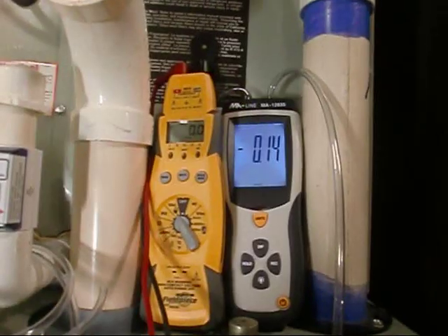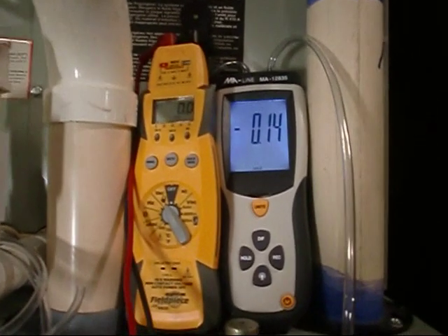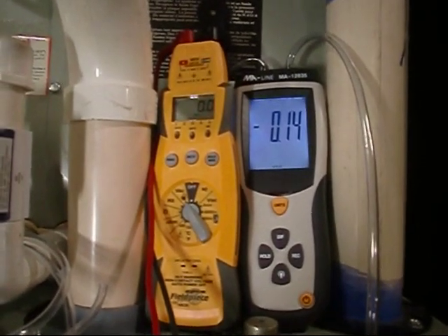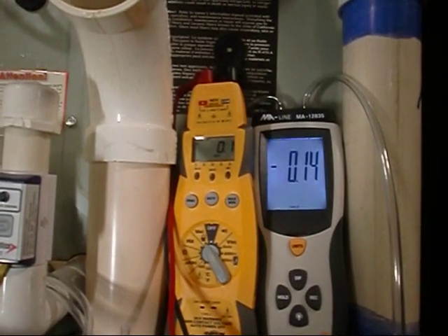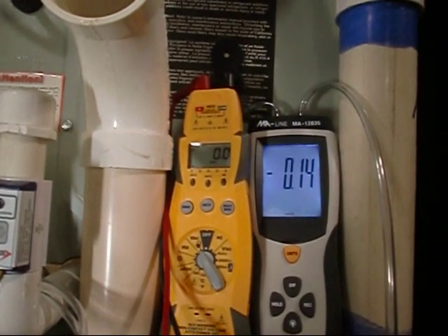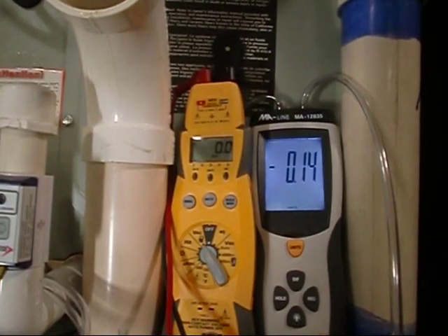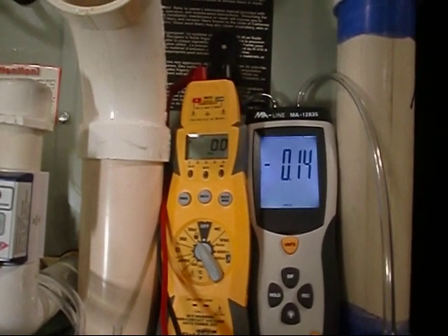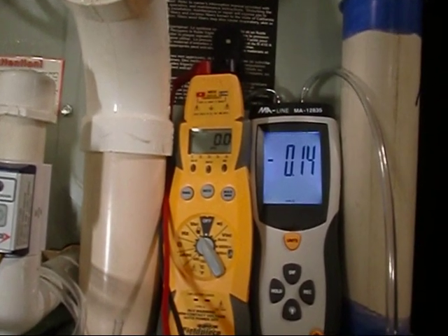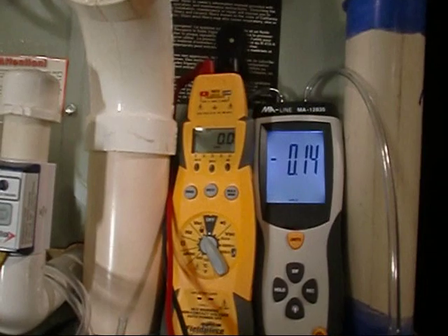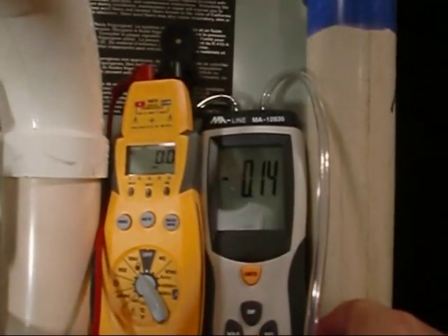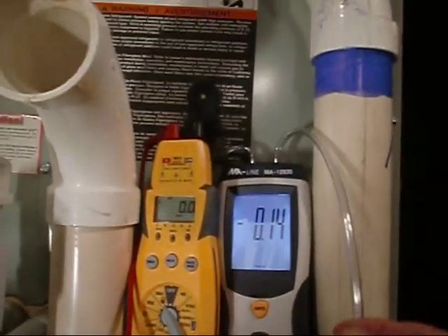I got everything hooked up now. We just did our little resistance test with the field piece there. We took our spade terminals off, and we hooked the field piece directly onto the correct terminals on the pressure switch. And when the switch was off, we had open load. And when we kicked the switch, we had her set to ohms, and she read a small amount of ohms, like 0.1 resistance.